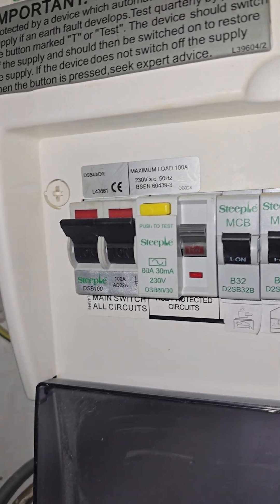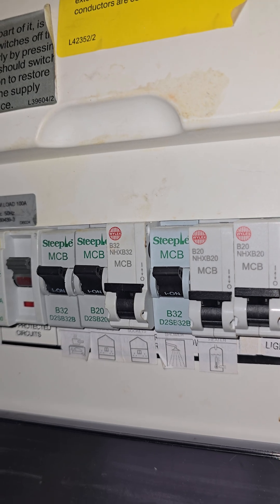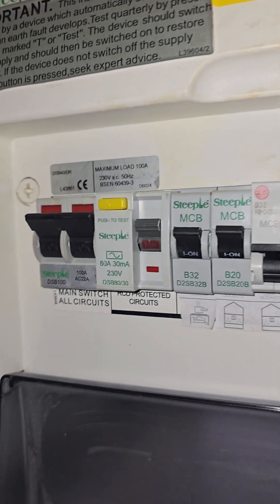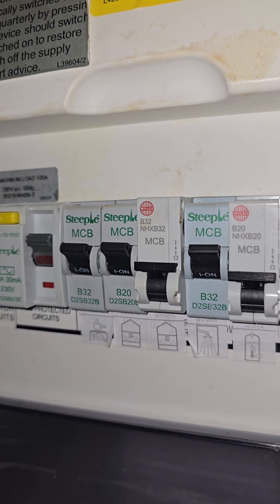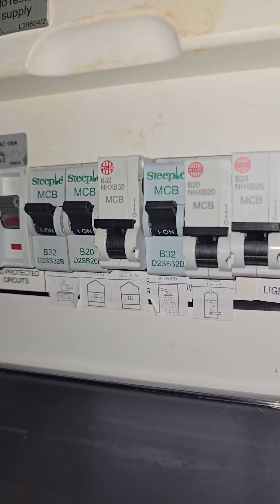Inside the fuse board we have a Steeple fuse board with some NHXB miniature circuit breakers. These NHXB breakers shouldn't really be in a Steeple fuse board — they haven't been tested by the manufacturer Steeple to work in their consumer units, so therefore it wouldn't meet the manufacturer's guidelines. So that's one thing wrong.